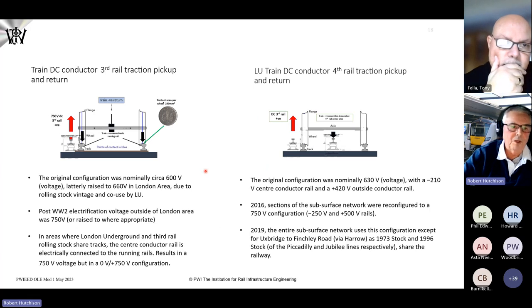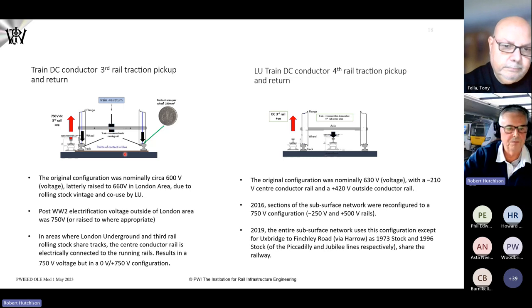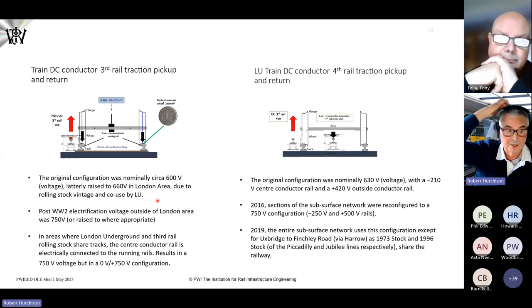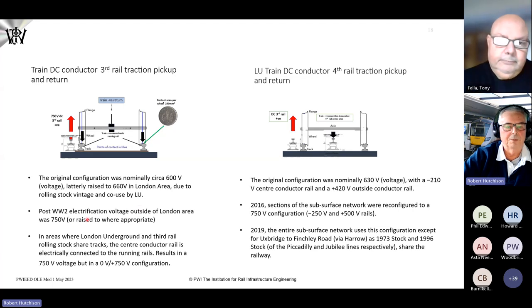For most people, the common setup has running rails with negative return via the axle brush from the traction system, and positive pickup on the outer side of the running rails at 750 volts nominally. In the early days it was 600 volts, but in the London area we went up to 660 because it was co-running with London Underground, and more recently, with the Kent Coast and Bournemouth line, we've now generally raised it up to 750 volts.